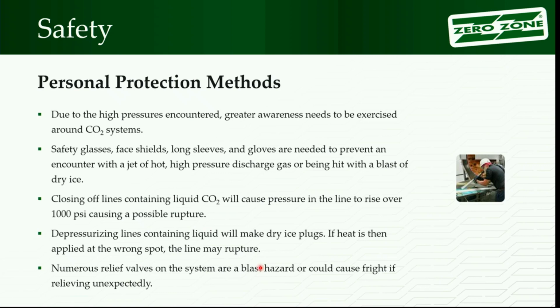Same thing comes into play if you have snow in something you're working on. If you're changing a filter dryer or a suction dryer, and you had some liquid in there that flashed off to snow, what don't you want to be doing with your bare hand? You don't want to be cleaning the snow out with your bare hand, right? You want to put some gloves on, use a tool or something like that. Otherwise, later on, you might have frostbite on your hand. Depends how much you get on. It could be bad or just the tinglies.